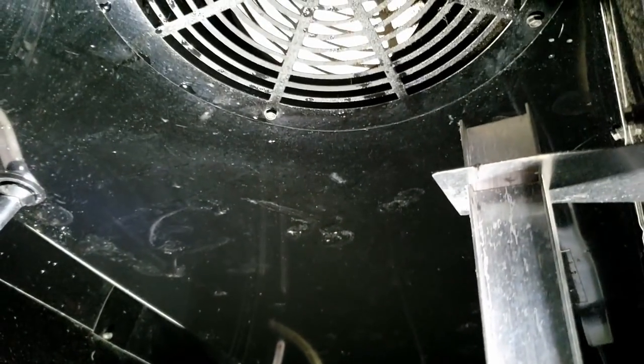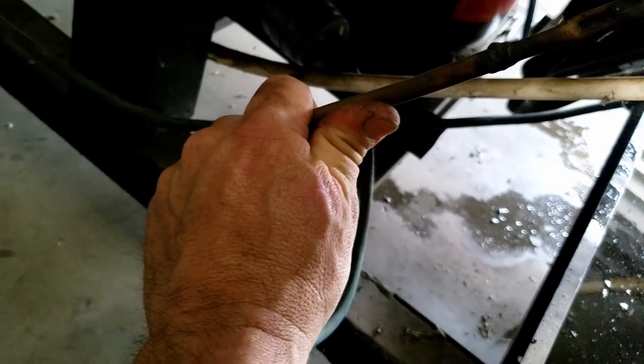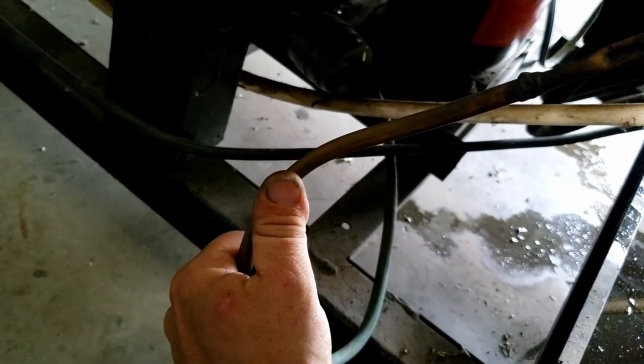They basically store stuff in their business in here and want it running right. Better plugged in — that fan's running, that one's running, compressor's going. I don't have a lot of extra room here, it's pretty stretched. The liquid line's not cold — it's definitely hot.